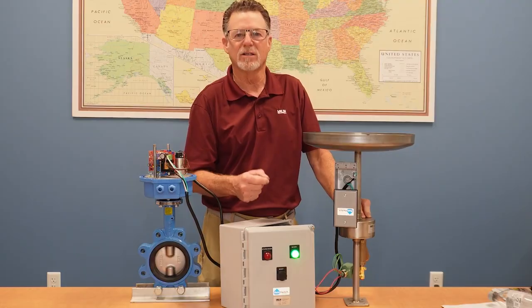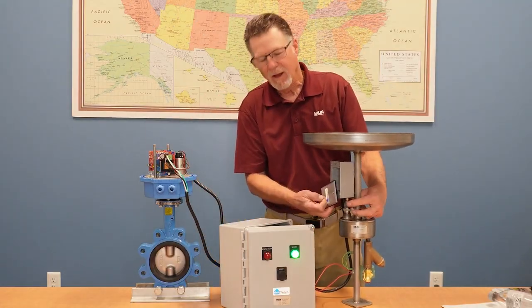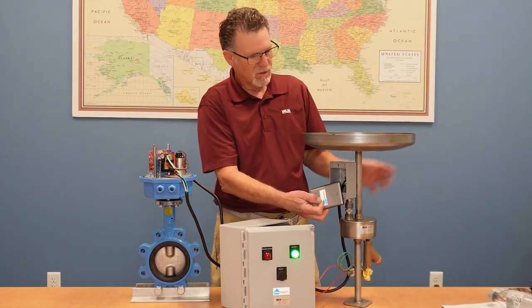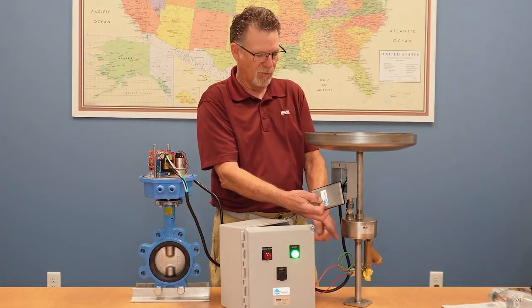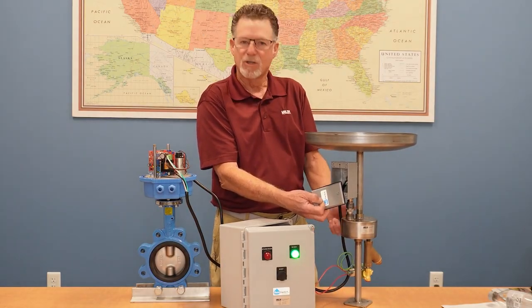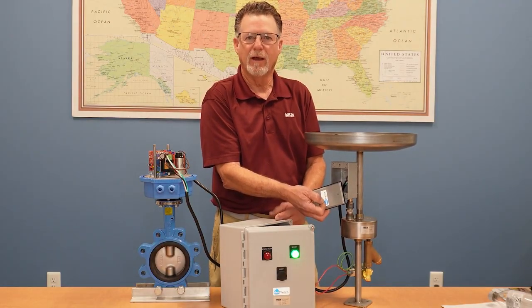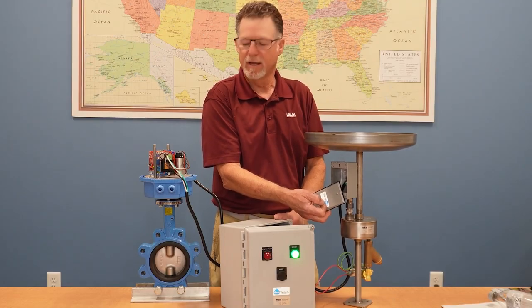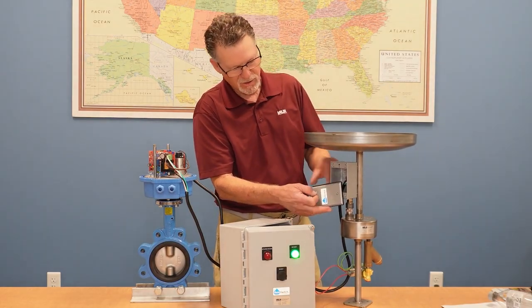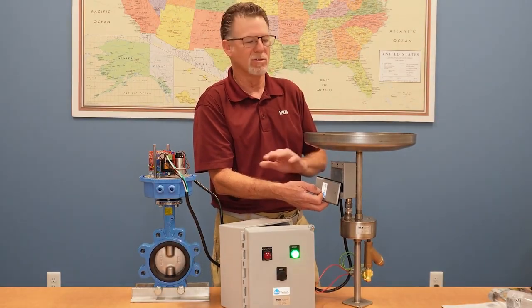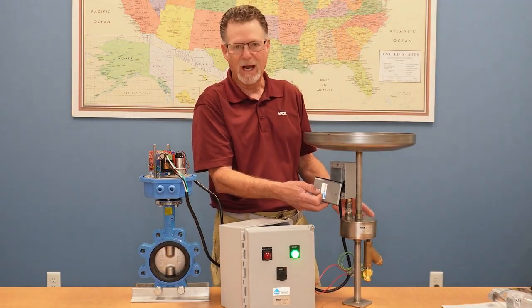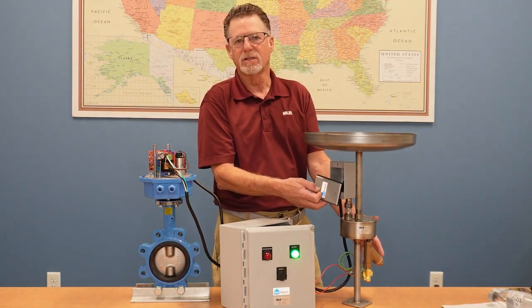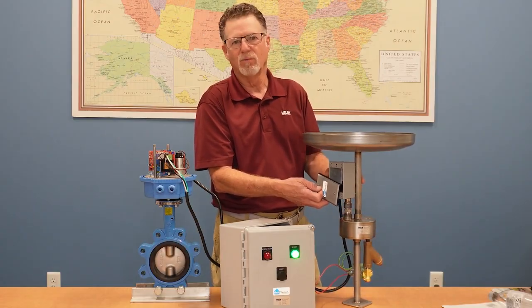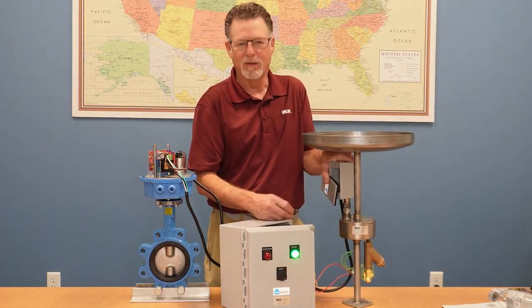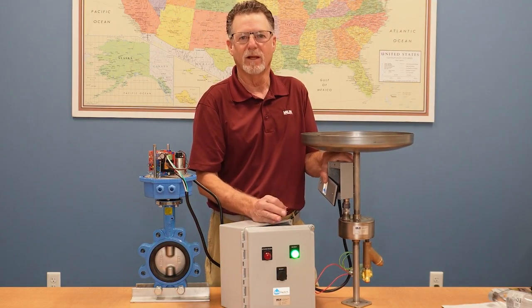The sensing probe here is nothing more than a stainless steel rod with a Teflon insulation around it from the connector. So what happens is the rainwater comes in the chamber. When it fills up to the point that it hits the probe, you get a short, and the relay detects that short, actuates, and switches the contacts to control the valve. So there really is nothing to fail on the rain switch. There's no moving parts. Every wetted part is stainless steel or brass. So as long as you keep the solenoid clean so you can reset it, there's just nothing to really go wrong with the rain switch. It's never the problem. If there's a problem, it's probably in the relay and the pilot station. We'll go over that shortly.